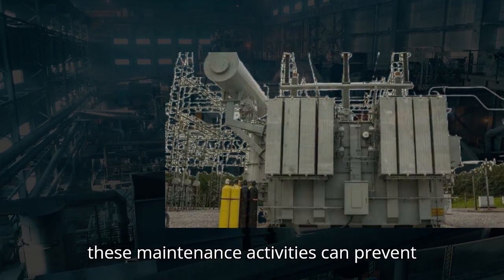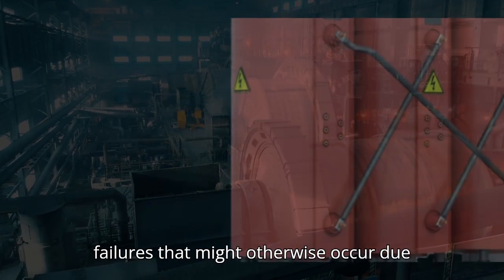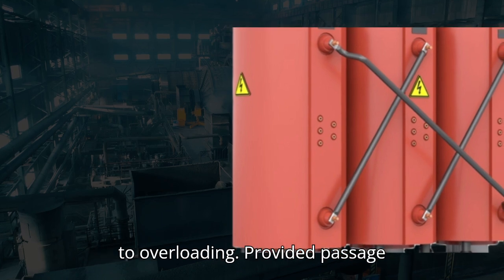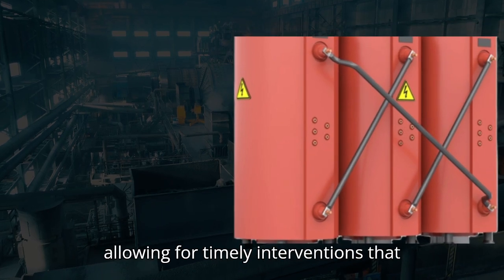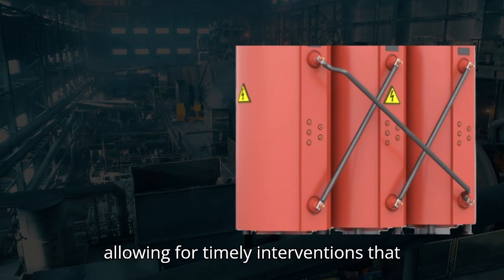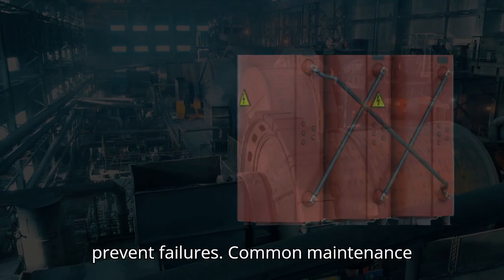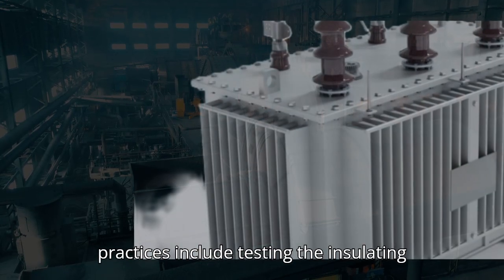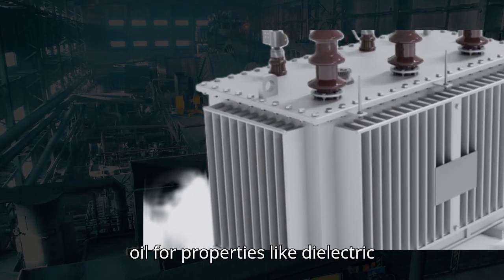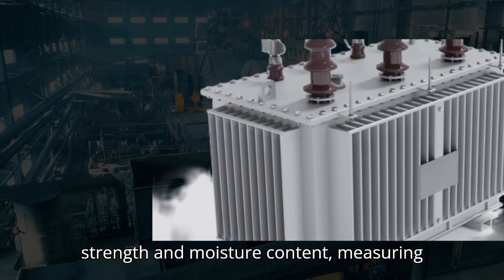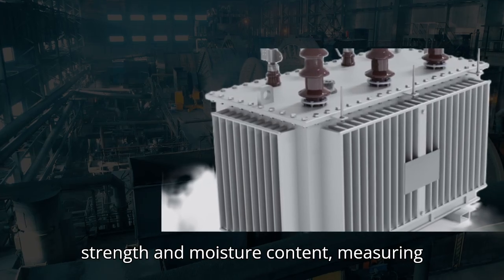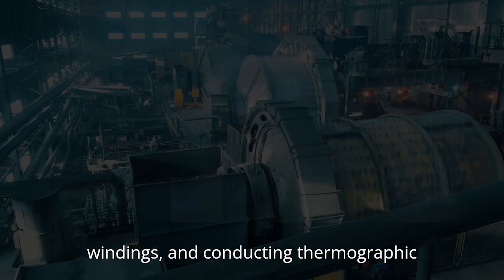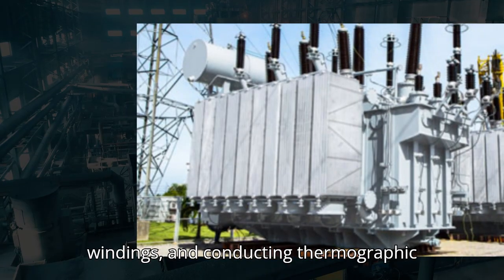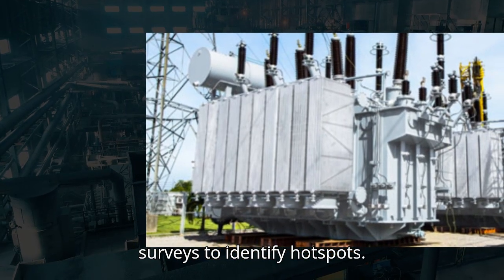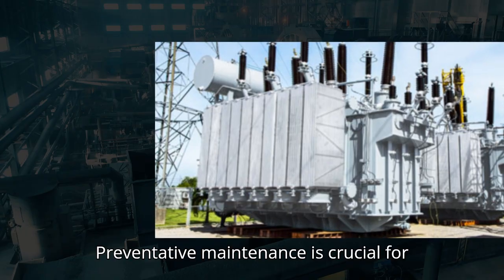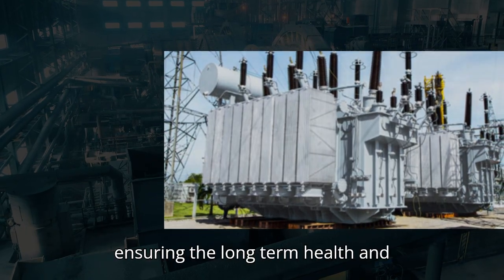Timely interventions based on the findings of these maintenance activities can prevent failures that might otherwise occur due to overloading. Common maintenance practices include testing the insulating oil for properties like dielectric strength and moisture content, measuring the insulation resistance of the windings, and conducting thermographic surveys to identify hotspots.